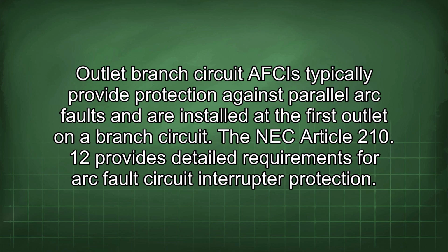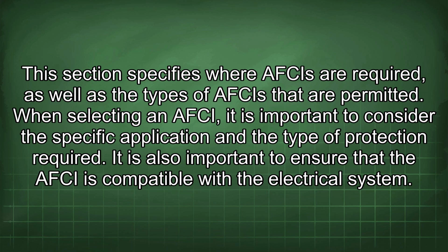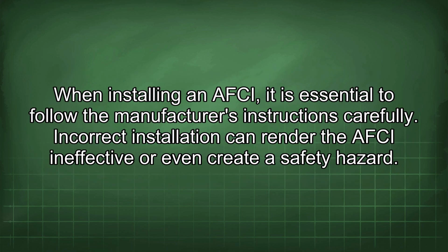The NEC Article 210.12 provides detailed requirements for arc fault circuit interrupter protection. This section specifies where AFCIs are required, as well as the types of AFCIs that are permitted. When selecting an AFCI, it is important to consider the specific application and the type of protection required. It is also important to ensure that the AFCI is compatible with the electrical system. When installing an AFCI, it is essential to follow the manufacturer's instructions carefully. Incorrect installation can render the AFCI ineffective or even create a safety hazard.